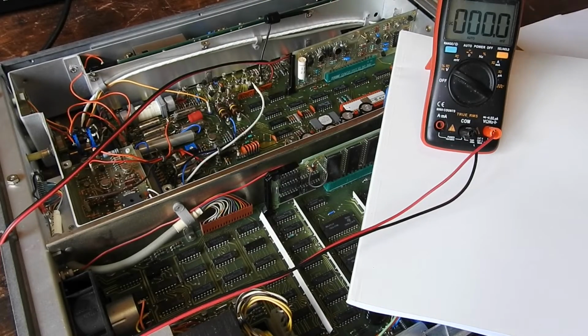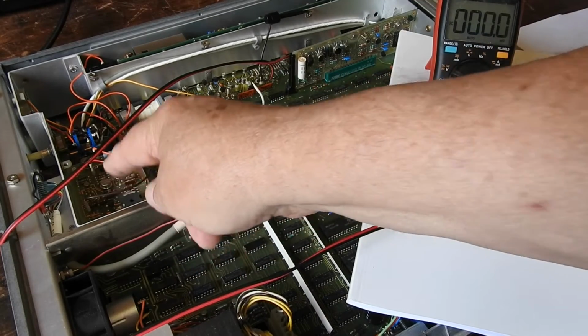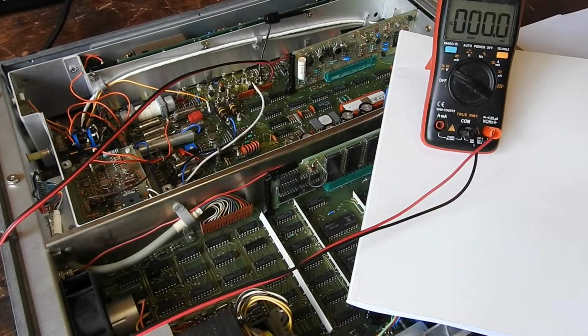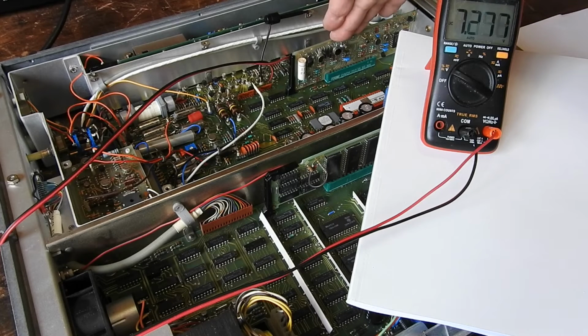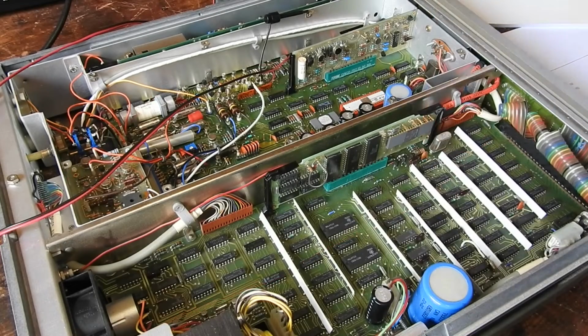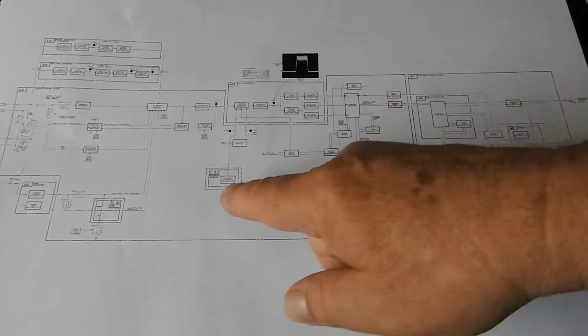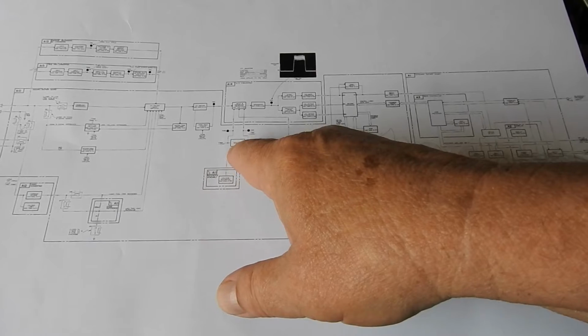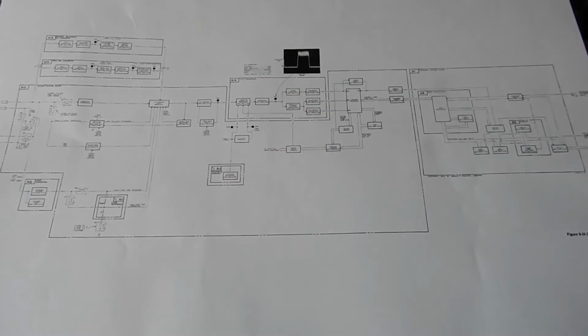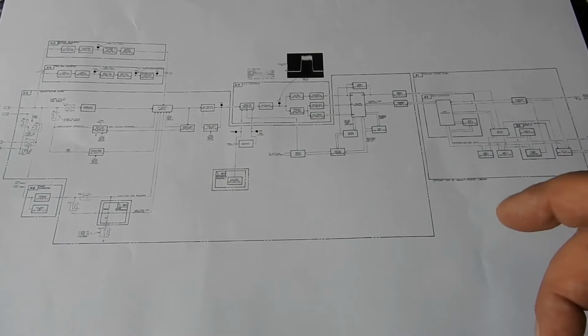Right, the 10 volts reference module's been reinstalled. We're looking at test point 8, which is its output, should be plus 10 volts. And we verified that it is coming out of the module as 10 volts when it's standalone. Turning on the power, and we see it's still being held down by something. We've shown that it wasn't the ADC board. I looked at that because the block diagram shows that the reference goes to an inverter, and there's test point 8 that we're looking at, and only goes into the ADC, and of course that's not correct. I knew there was something wrong about that because it doesn't work like that in the 3456. The reference also goes into the switching network.